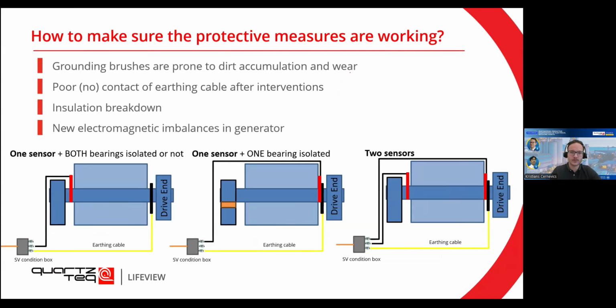First of all, your grounding brushes are prone to accumulation of dirt and wear. So at some point, your grounding brushes are not pushing on the shaft as much anymore, and less of the current is actually diverted. You can also have issues with the poor or no contact of the earthing cable or the earthing strips. Maybe after some intervention, it's not put back on. You can also have insulation breakdown on some of your bearings, or maybe something has happened with your machine. There are new imbalances in your rotating machine, and this will give rise to shaft voltage.